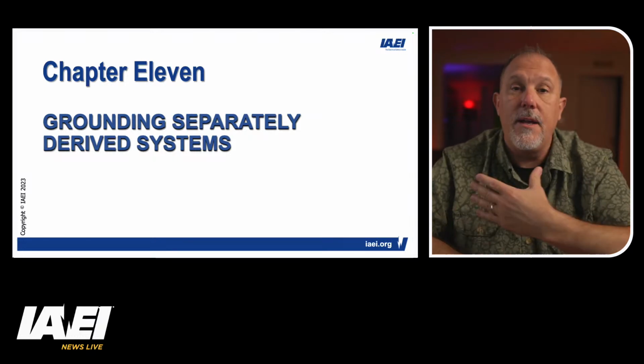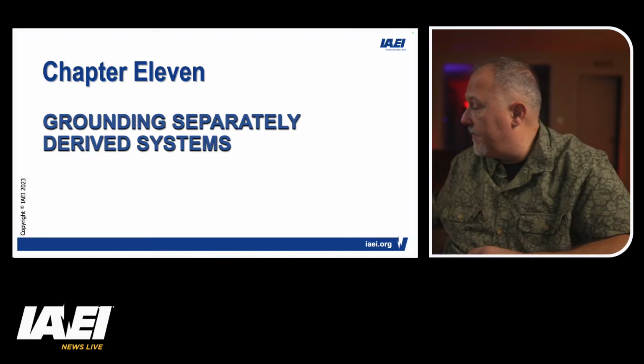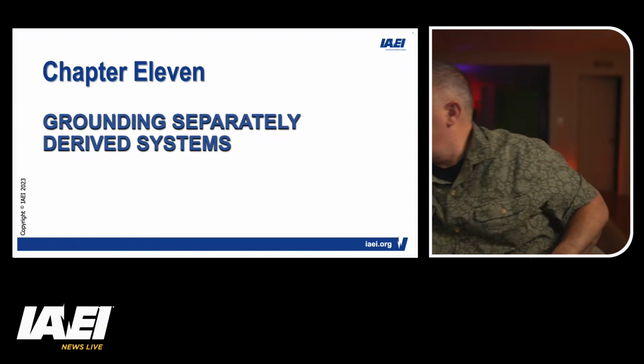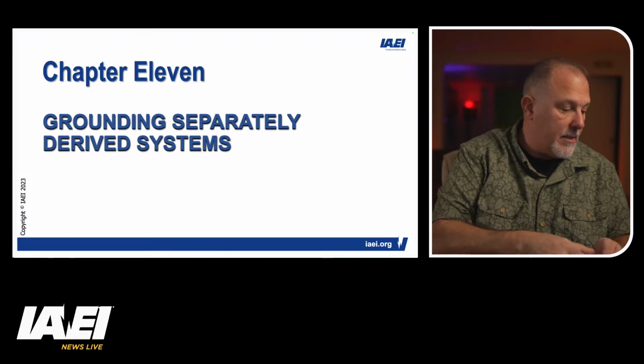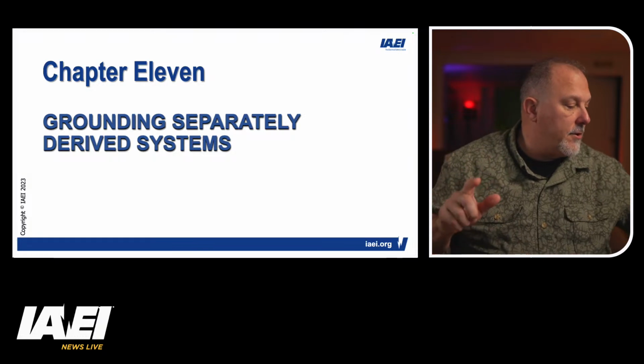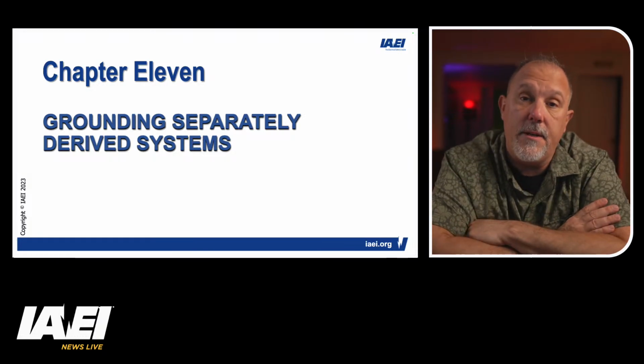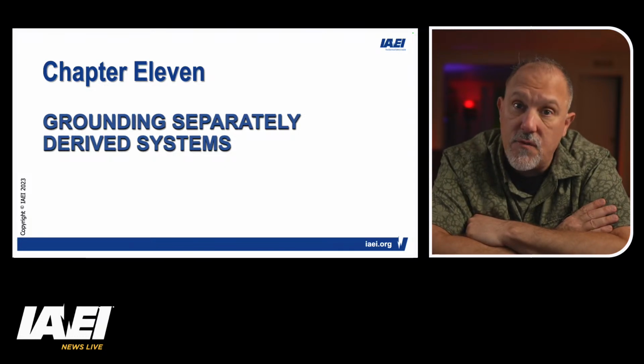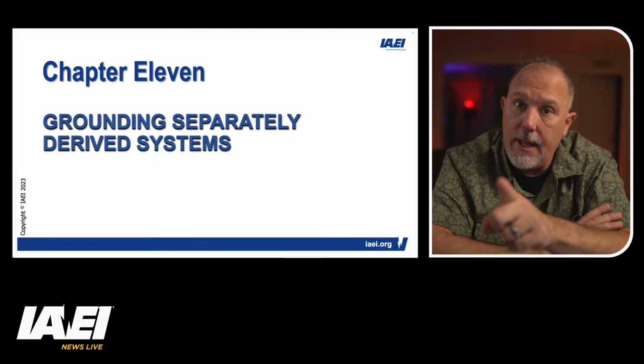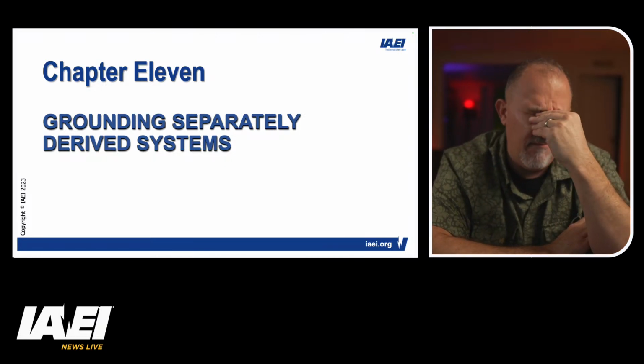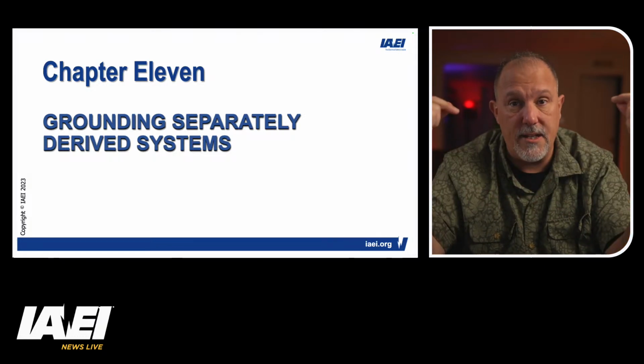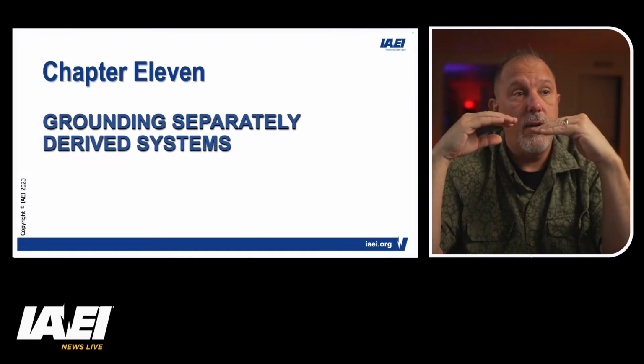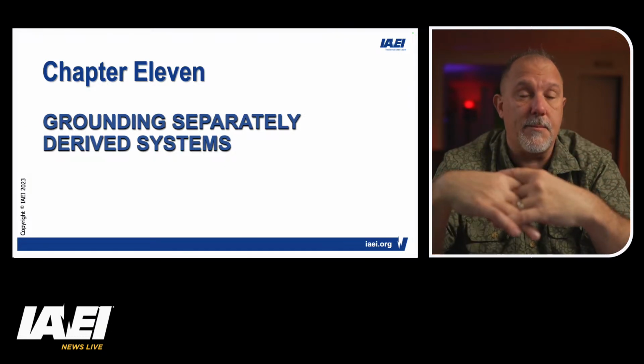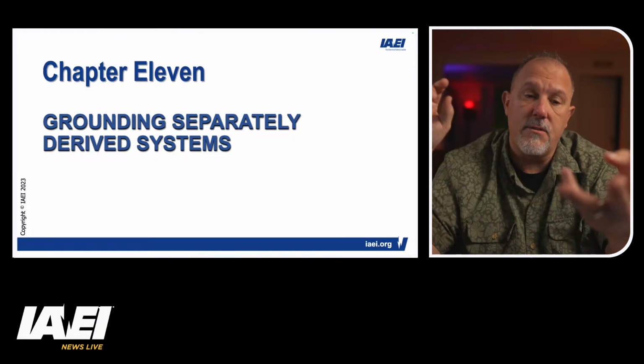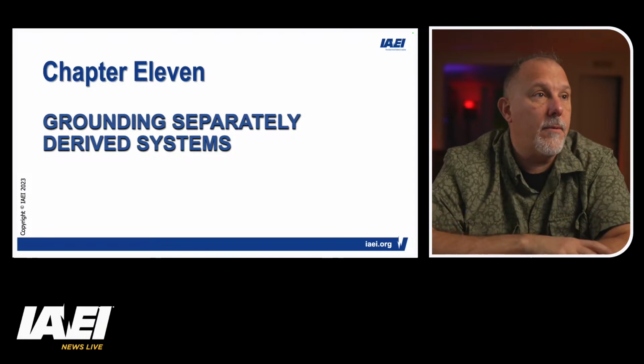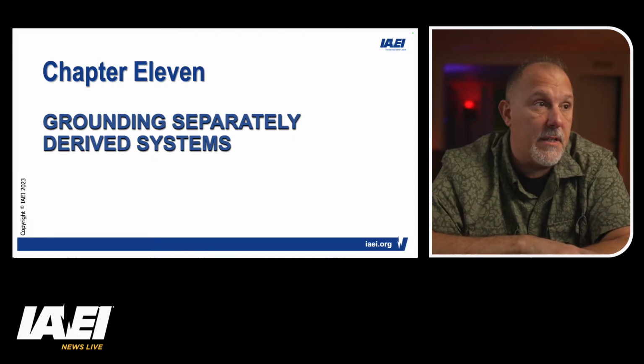But the biggest and easiest example for me is... I gotta move my phone, because whenever it vibrates, I hear that. The other good example for a separately derived system, in my opinion, is a delta to Y ground transformer, delta delta transformers, Y to Y transformers, not an autotransformer, because autotransformers share windings between the primary and secondary. So the autotransformer is not a separately derived system. Your Y to Y, delta to delta, delta Y ground, etc. are separately derived systems.